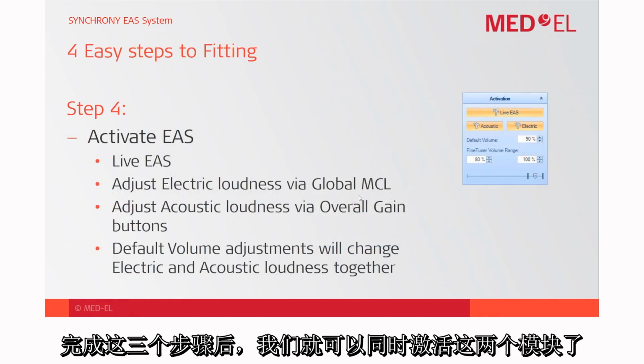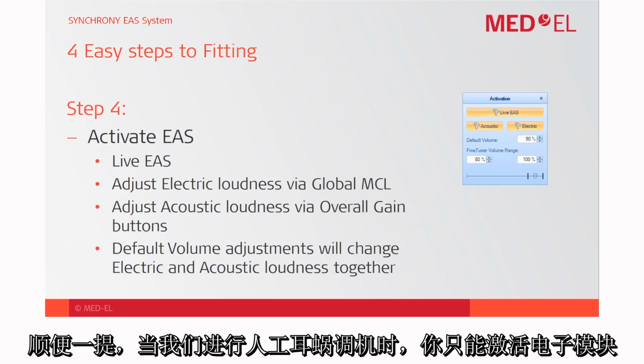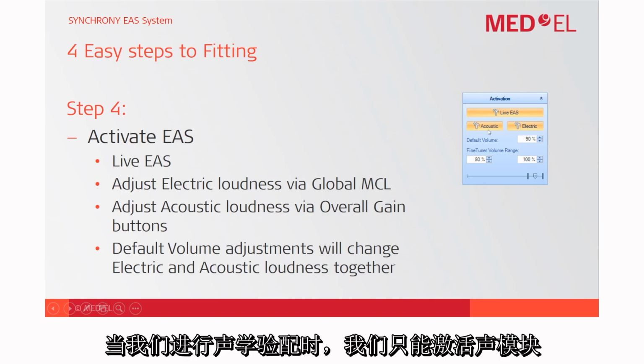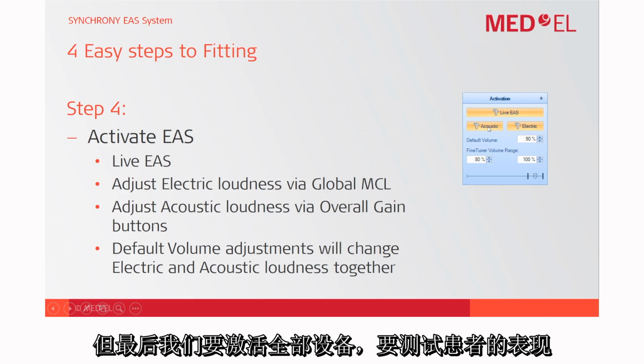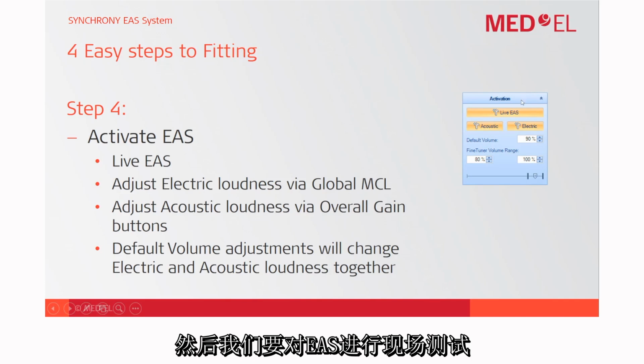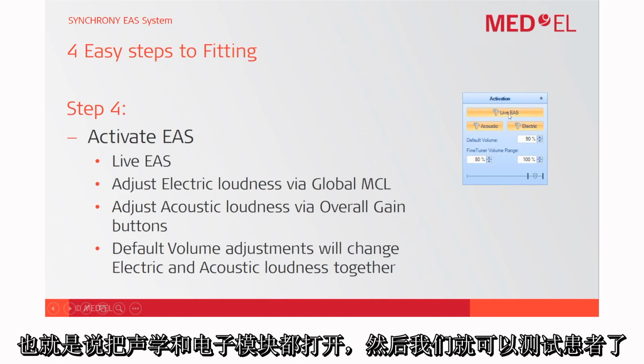So once we have done the 3 steps, now we can activate both the units simultaneously. Just for you also to know, when we were doing the cochlear implant fitting, you could have only activated the electric side, or when we were doing the acoustic fitting, we could have only activated the acoustic side. But in the end, when we want to activate the device altogether and we want to test the performance of the patient, then we want to go live EAS so that both the acoustic and electric units are on. And now we can test the patient.